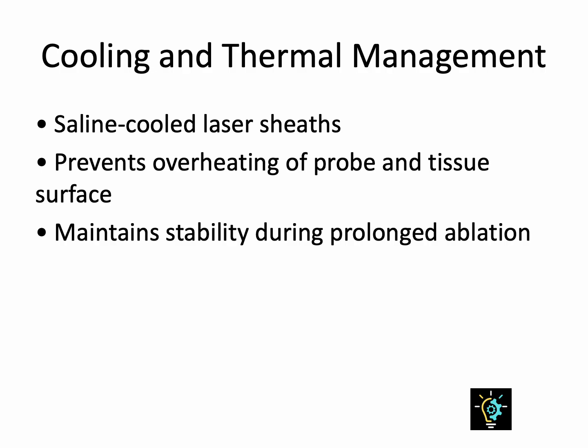Thermal management ensures that the system ablates target tissue without damaging adjacent structures. Engineers design cooling sheaths that circulate sterile saline around the laser fiber, maintaining consistent temperature gradients. The coolant removes excess heat from both the probe and surrounding tissue near the entry point. This prevents charring and optical fiber degradation. Real-time temperature readings from thermocouples inside the probe feed into the workstation, enabling precise control of ablation zones. This combination of passive and active cooling mechanisms is what allows LiTT to operate continuously and safely within a narrow therapeutic temperature window.